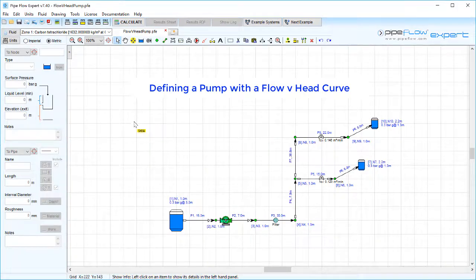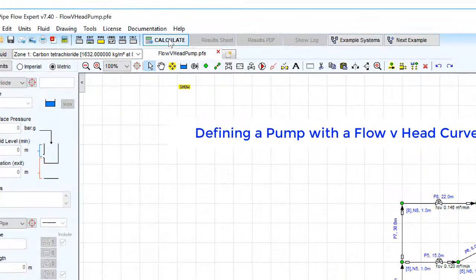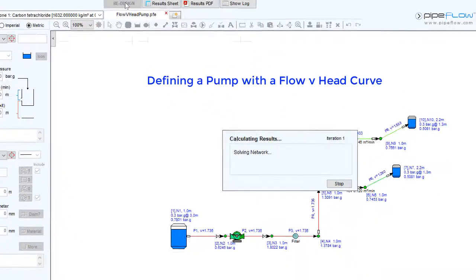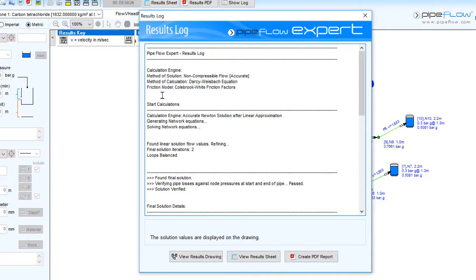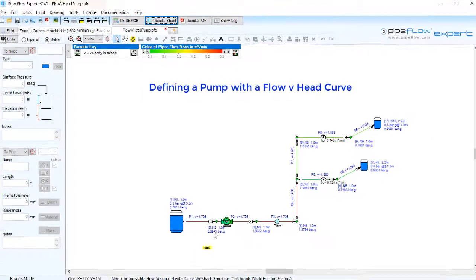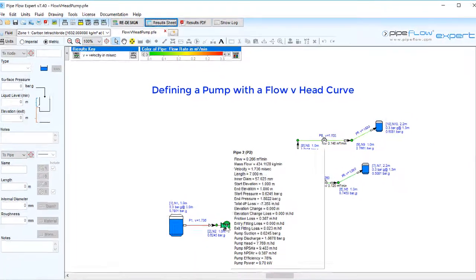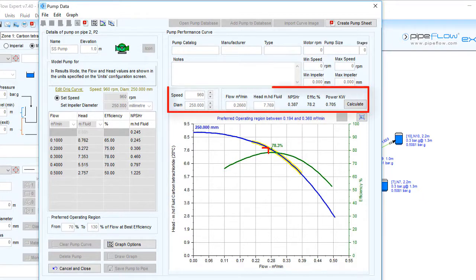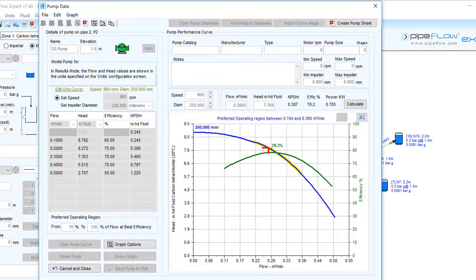The system can now be solved and the balanced operating point of the centrifugal pump will be determined. The pump will produce a flow rate and pump head to match the frictional resistance throughout the system. The duty point will be identified on the performance curve for the operating speed of the pump.